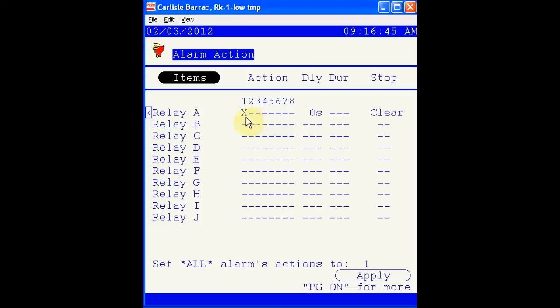Here you can see we've selected any alarm with action number 1 to go to alarm relay, here labeled as relay A. There's no delay before the alarm can activate the relay, and the relay will stay on until all alarms have cleared. We can find more information about this alarm relay by selecting this arrow to the left of relay A.